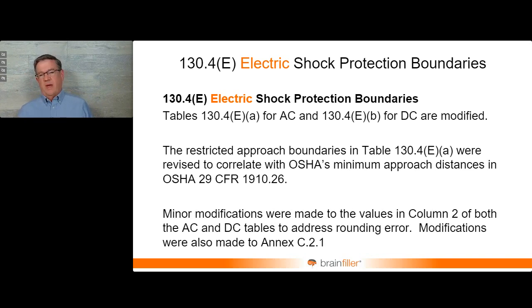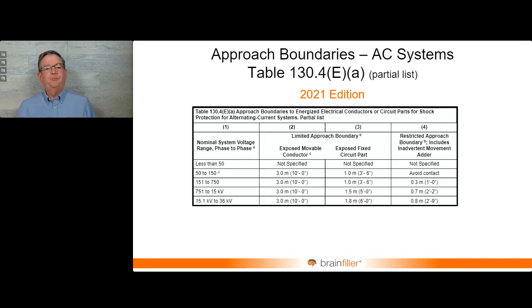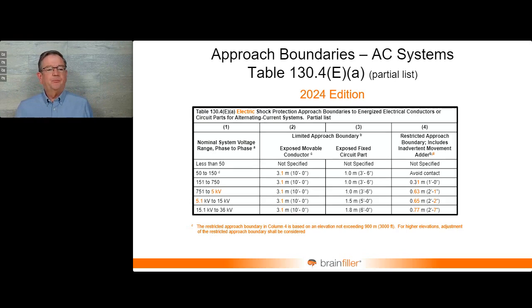So this is what we had in 2021. This was the table where you would determine the limited approach boundary and the restricted approach boundary. These are the numbers that we've had for a very long time. But now, a couple things have happened. The 751 V to 15 kV range was divided, so it's now into two different voltage ranges. And over here, the exposed movable conductor was rounded up.